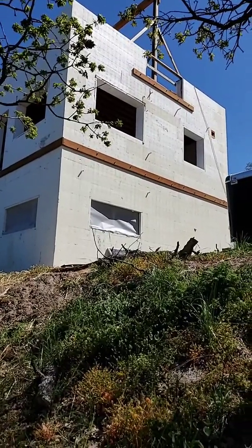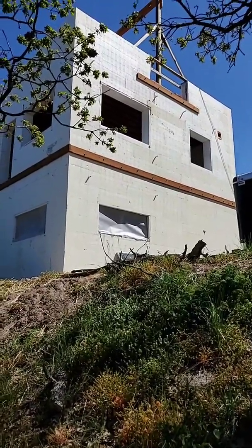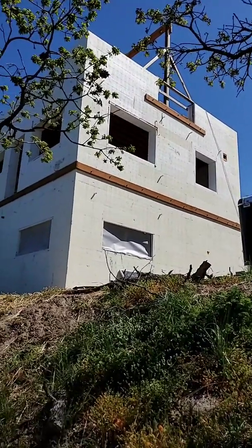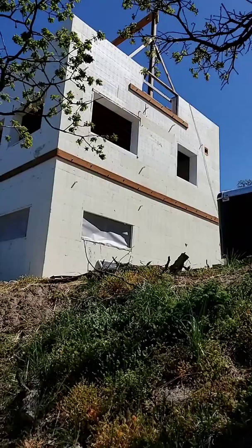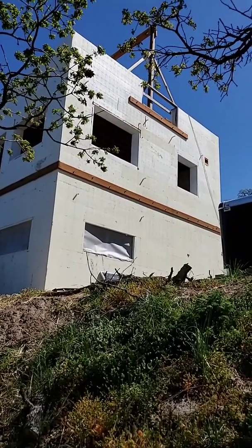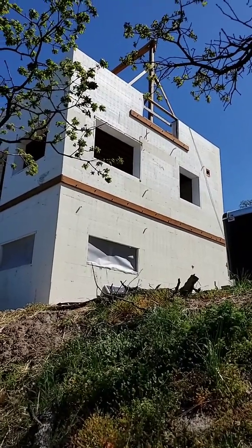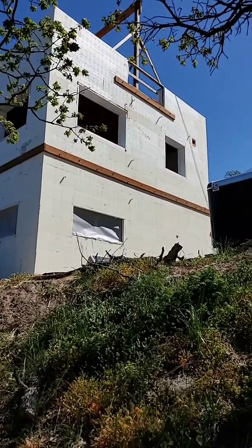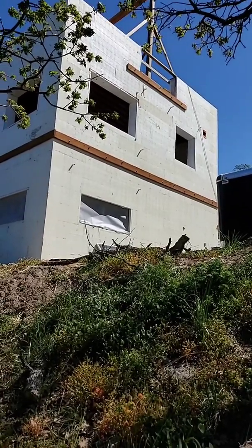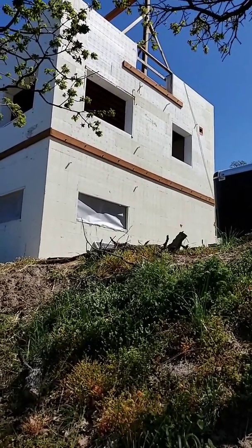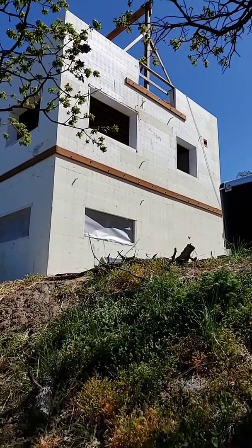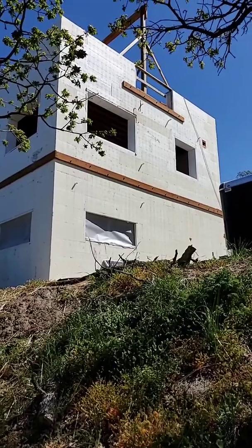And so you have the conduit running from a junction box where your electrical panel is, maybe in the garage or basement, and then running all the way up to your roof. If you have an attic space with insulation on the flat part, make sure that the second junction box and the conduit extend above the insulation so that when they want to install solar later, they can find it.